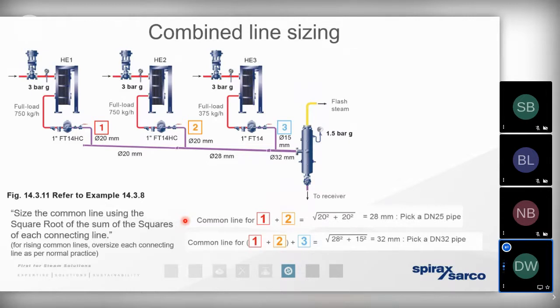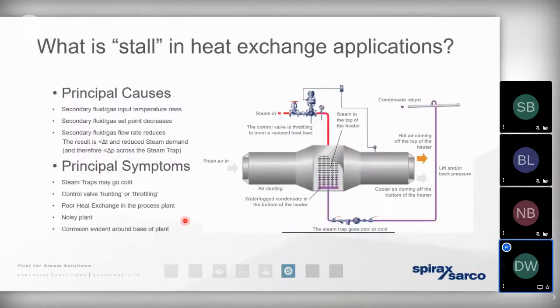So we've mentioned that a steam trap is a passive device. We do need a good motive energy in the steam to push that condensate away. So of course we know that in a certain number of processes, it may well be that we only require a very small amount of energy in that steam to add a small amount of energy to a process. So the example we've got here is an air handling unit. Now, it could apply to any other heat exchanger. I'm just using this as an example. Let's say we were using a steam coil to heat air coming from outside a building to heat a production line or to heat an office space.